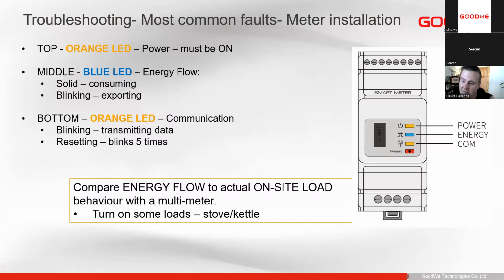So the top orange LED is the power that needs to be on. So if we have power to the smart meter, that needs to be on. If it doesn't come on, we would obviously know that it's faulty. So that can happen. Next is the blue LED. That's our energy flow. When it is solid, we are consuming power from the utility. So if your inverter's off, there's no PV production, no battery consumption, everything should be coming from utility, and we should see that light solid. If that light is flashing, we know it's exporting. So if there's no inverter connected yet and that light is flashing, then we know we have a problem we need to solve. And the last is the COM LED, so if it's connected to the inverter and communicating, it will just slowly flash the whole time.